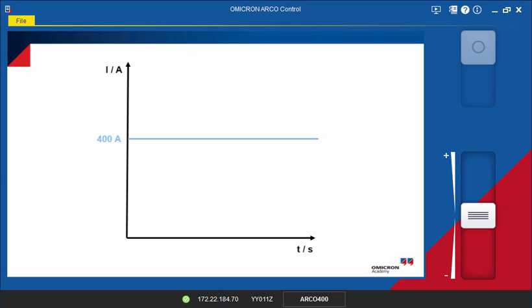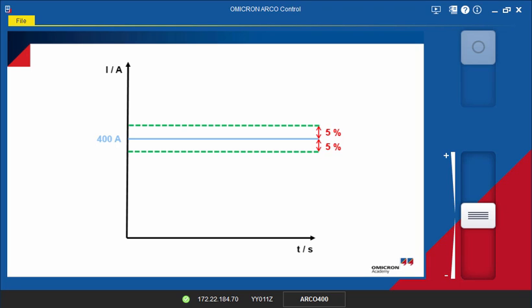The blue line indicates the pickup value. According to the controller's manual, the pickup value has a tolerance of 5%. The upper and lower limits of this value are represented by green lines in the diagram. The aim of this test is to check that the pickup value is contained within the tolerance band.